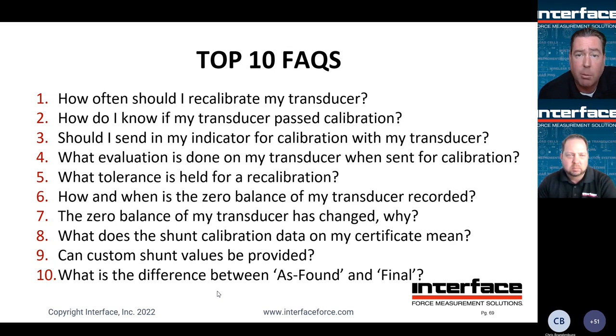What does the shunt calibration data on my certificate mean? So the shunt calibration is performed prior to the load cell coming out of the rig on a calibration run. They'll run, let's say, a tension run, then they'll perform the shunt with the load cell unloaded, and prior to taking that zero balance.